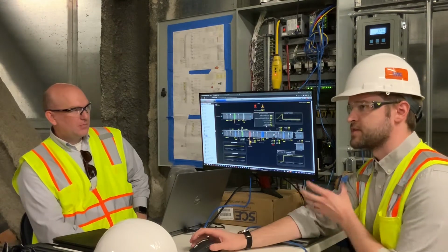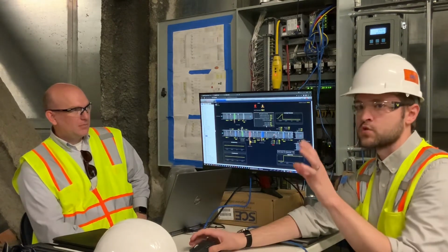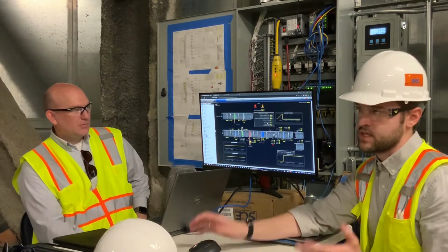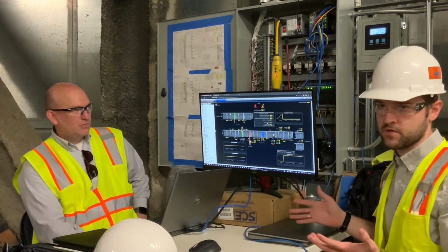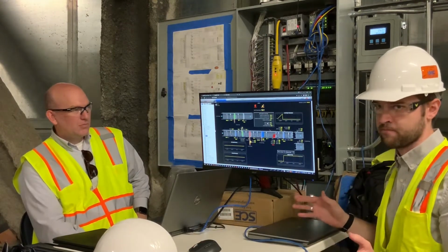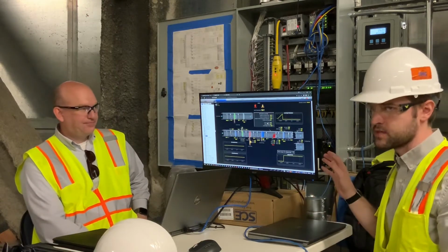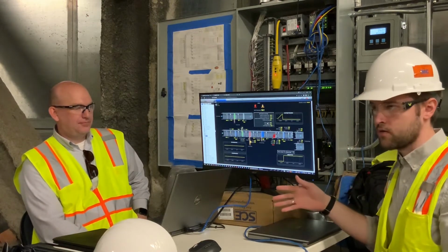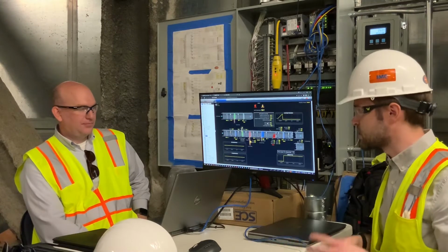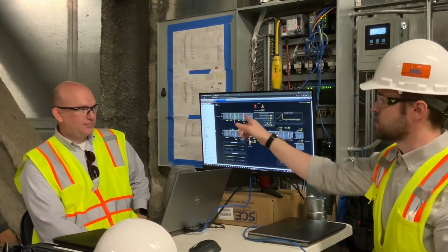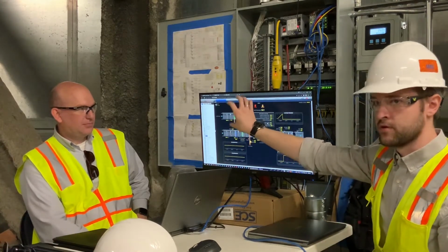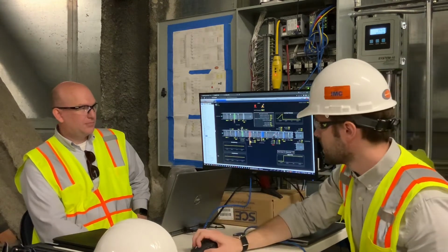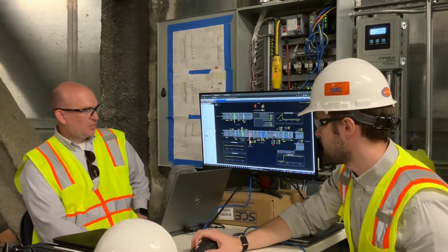There's a lot of similarities between this unit and air handlers 1 through 4. There are some important differences. This is the only air handler for the 12th floor. It's not a common plenum with 3 other units. If this unit goes down, you lose supply airflow on the 12th floor. It has 2 supply fans. The exhaust side doesn't have its own built-in exhaust. That's actually the lab exhaust fan up at the roof level.